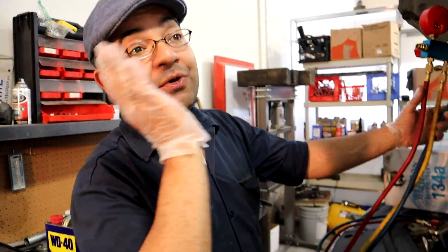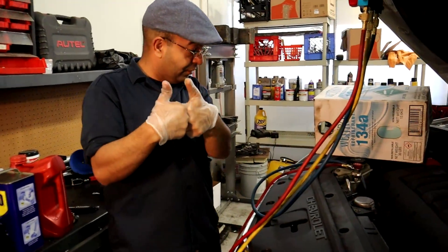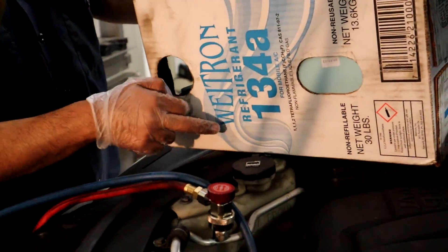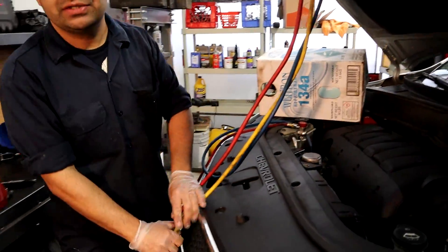This has been sitting for more than one hour now. As you can see, the needle is in the same place. That means we are good to go for refilling the system with Freon R-134A.